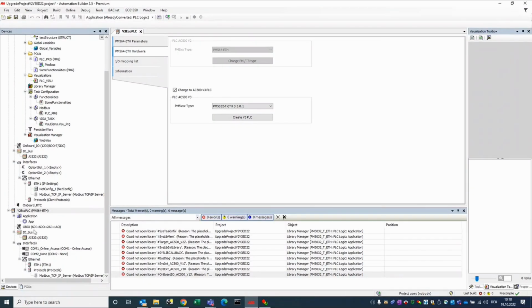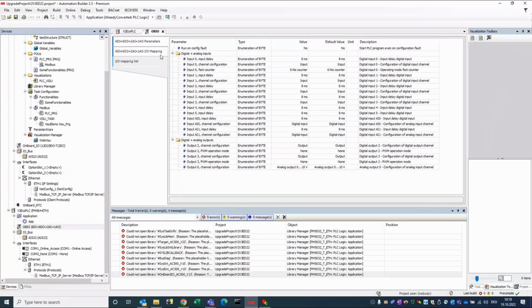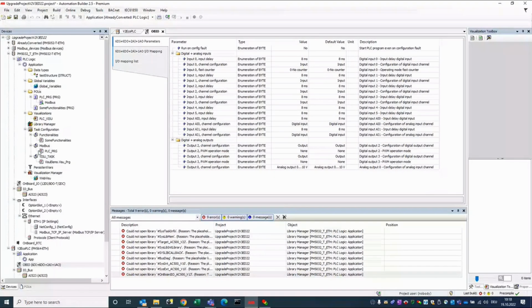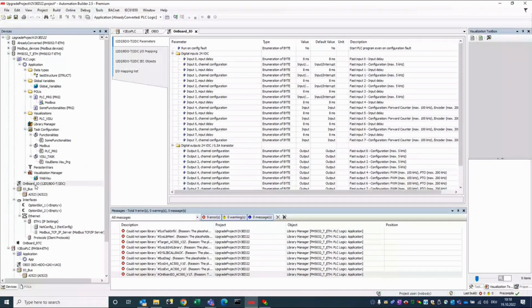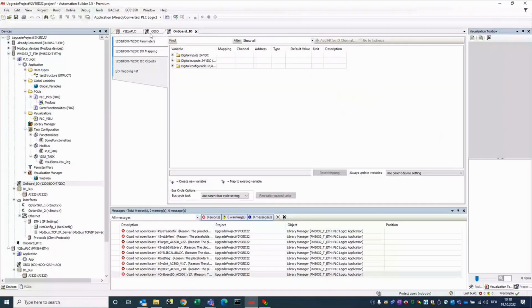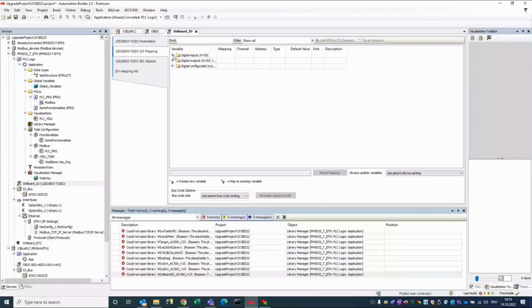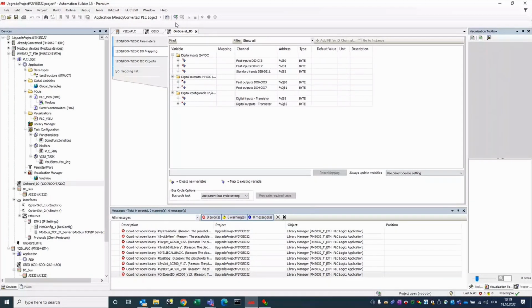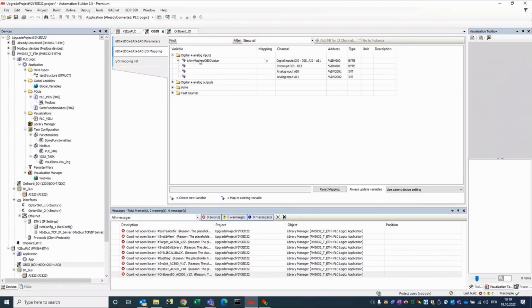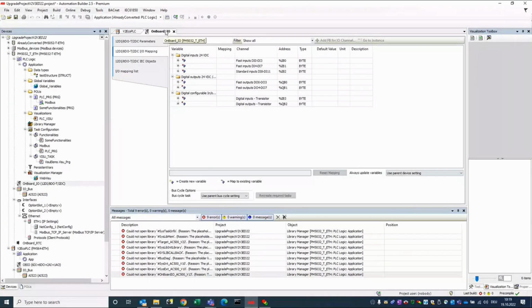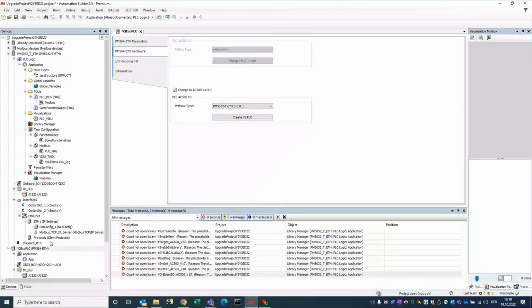The only thing to know is the onboard I/O. So here you had 6 DI, 6 DO, 2 AI, 1 AO. This is looking completely different in the V3 because we have other possibilities, more channels, faster channels, other channels. So there's no one-to-one mapping possible. So if you had mapped values in the V2, they will not be available somewhere in the V3 PLC. So these variables need to be mapped by hand. But it's only a few variables, so not that many things to do.